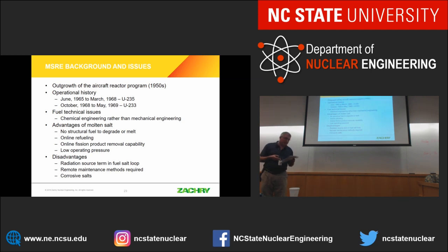Of course, there are some disadvantages as well. First of all, your fuel's in the loop. Your fission products are in the loop, which means that unless you have a death wish, you're not going to go into the area of the loop. The radiation levels are just going to be too high. You're going to have to use remote maintenance. Also, the salts are very corrosive, so you have a big materials issue with trying to make sure that the metal out of which it's built will survive. And they did study that with the Hastelloy N that they used.